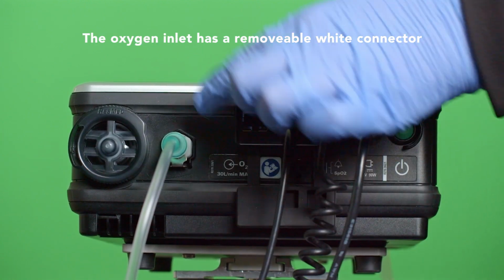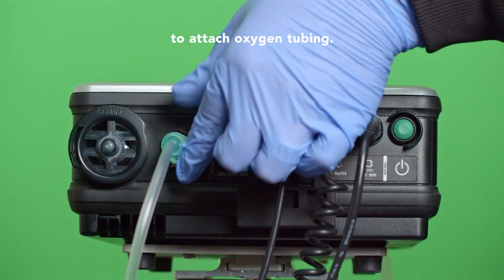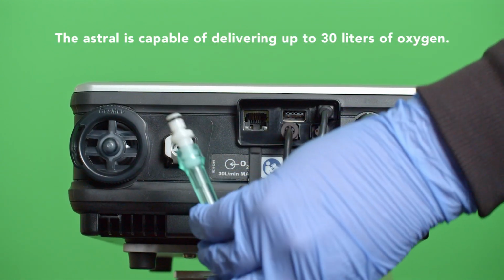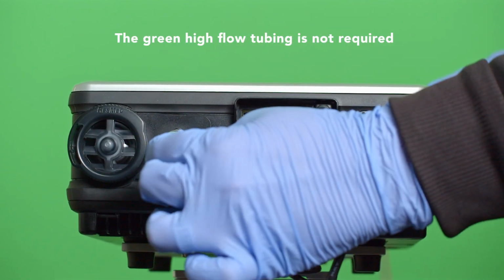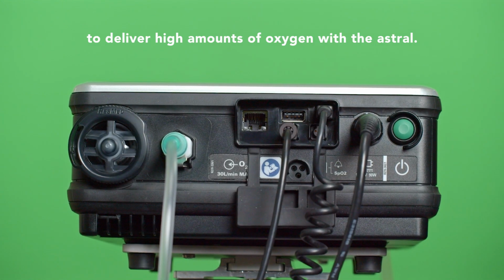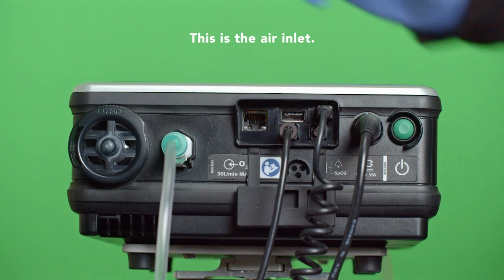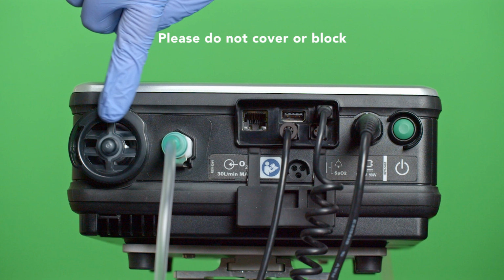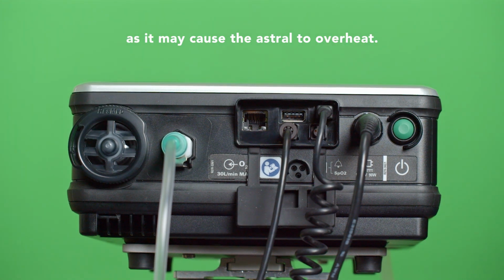The oxygen inlet has a removable white connector to attach oxygen tubing. The Astral is capable of delivering up to 30 liters of oxygen. The green high-flow tubing is not required to deliver high amounts of oxygen with the Astral. This is the air inlet. Please do not cover or block it, as it may cause the Astral to overheat.